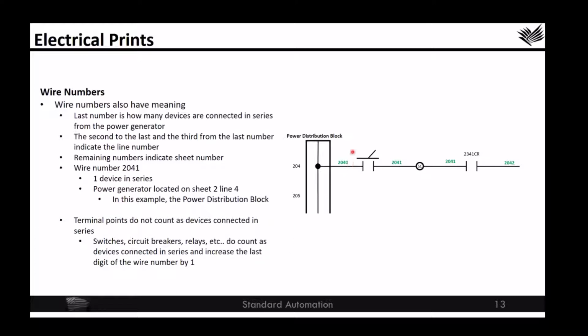So after I've taken off the last number for the serial devices, and I've taken off the second to the last and the third to the last digits for the line number, I then get the remaining numbers left for the sheet number. So in this case, it would be on sheet 2, line 4, and have 0 connecting devices in serial before the power generator. Wire number 2041 is going to have 1 device in series, and the power generator is going to be located on sheet 2, line 4. In this case, the power distribution block.